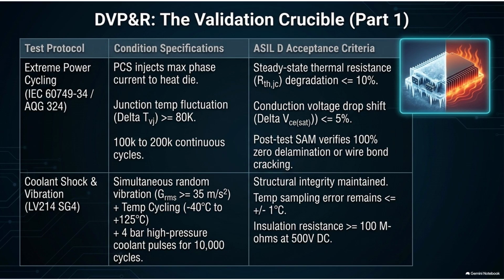Precisely. And they take the exact same ruthless approach to applying the thermal paste, the TIM. The protocol explicitly states, no human hands allowed. The application must be fully automated. Because a human with a syringe is incredibly inconsistent. The paste is applied by fully automated stencil printing machines, followed immediately by 3D laser topography scanning. Lasers now. Yeah, a laser sweeps across the wet paste, measuring its height at thousands of points.